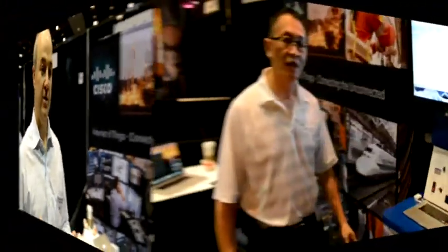In the demo that we have for this conference, we're working with BitStew. In the last few months, we've been able to port their IOX core system into the Linux operating system here. What it's doing is performing data analytics in real time between the SCADA slave and the SCADA master across the network. So when an event happens, for example, if the Capacitor Bank Controller was to have some problem or issue, this would be seen by the BitStew analytics engine that's running here inside of the router, and it could create alerts. This is part of the concept of fog computing, where we're distributing compute right down to the edge, right onto the pole top.